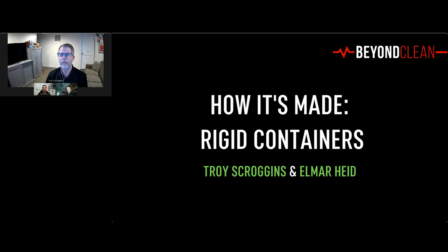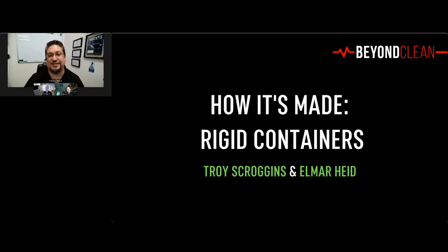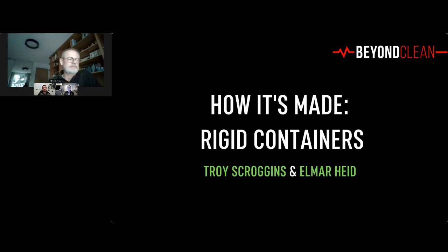Elmar, is that the same standard in Europe, the 18 inch stacking limit? No, we do not have a standard for the height of stacking, but practically we follow the same principle. It has to still be safe for the use and for the patient at the end of the day, so we end up with the same principle. Also, it's not written or defined in an ISO standard.